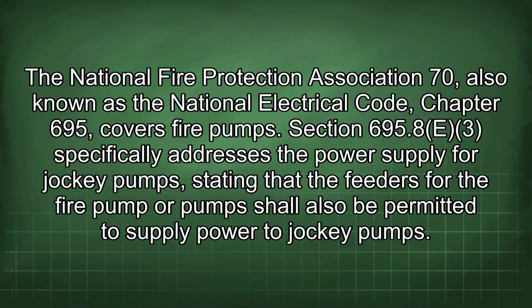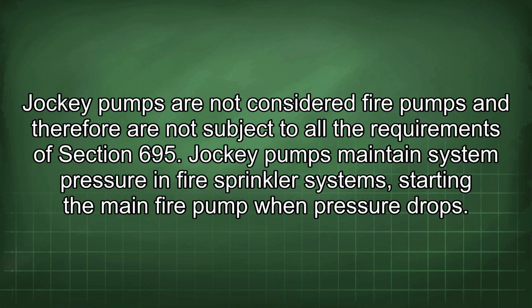The National Fire Protection Association 70, also known as the National Electrical Code, Chapter 695, covers fire pumps. Section 695.8(E)(3) specifically addresses the power supply for jockey pumps, stating that the feeders for the fire pump or pumps shall also be permitted to supply power to jockey pumps. Jockey pumps are not considered fire pumps and therefore are not subject to all the requirements of Section 695. Jockey pumps maintain system pressure in fire sprinkler systems, starting the main fire pump when pressure drops.